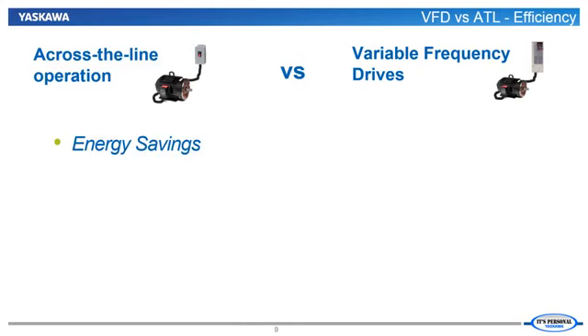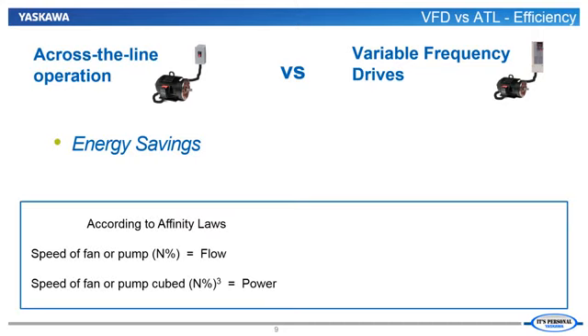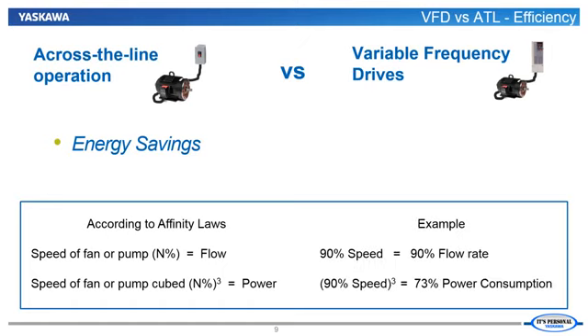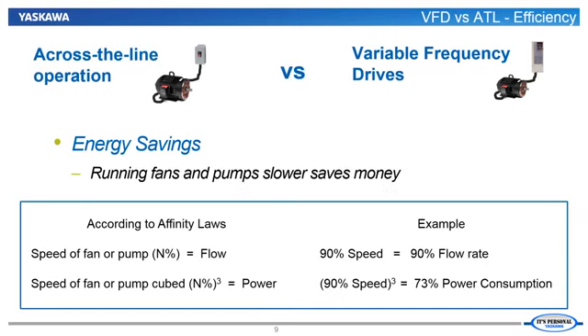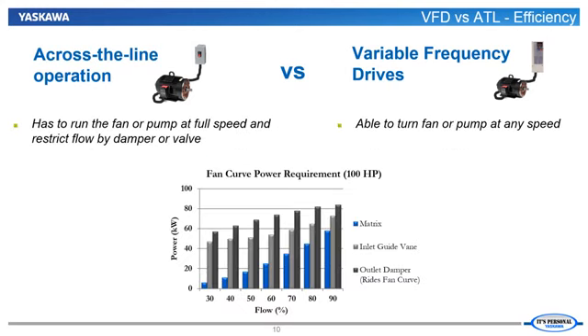If we want to compare the efficiency of using a VFD on a fan or pump versus running across the line, we need to look at the amount of energy used by each method across their realistic operational range. Our aid in this comparison is the set of affinity laws, which govern power usage for fan and pump loads. According to the affinity laws, if we drop the fan or pump speed by 10%, we actually drop the power used not by 10%, but by 27%. So the slower the fan or pump runs, the greater the energy dollars saved.